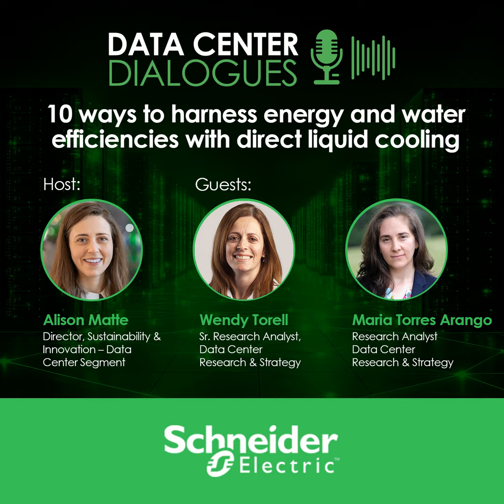This visibility is what allows teams to eventually move from fixed conservative operating points, like those Wendy mentioned with temperature, to optimized parameters, and eventually to dynamic control, adjusting pump speeds, temperatures, and cooling capacity based on real demand. This is how you improve efficiency without increasing risk, and how you maintain performance as IT requirements evolve.